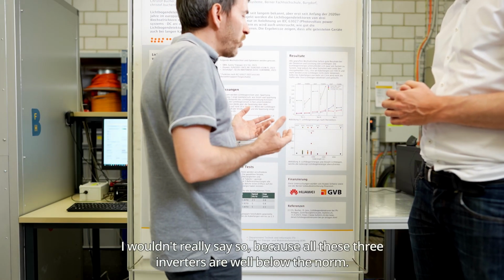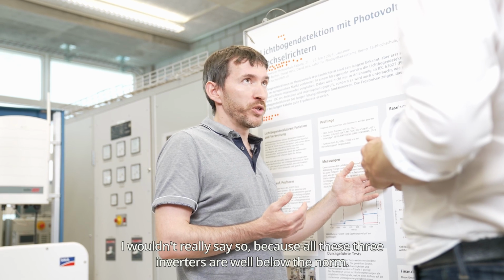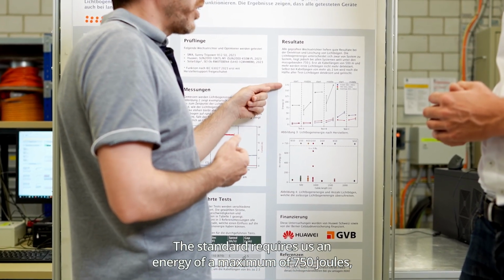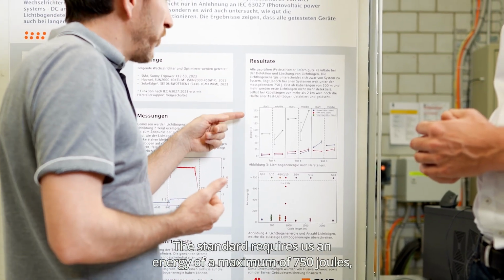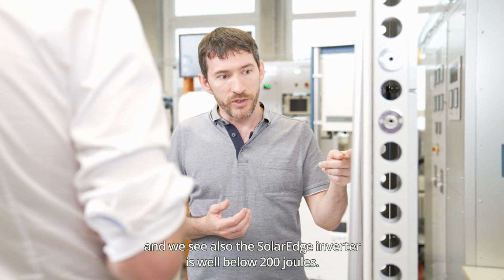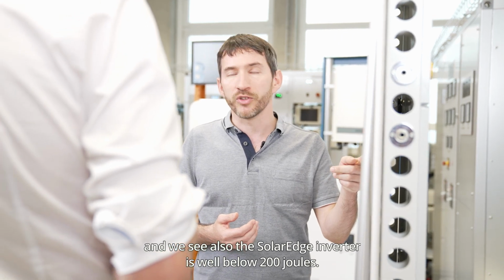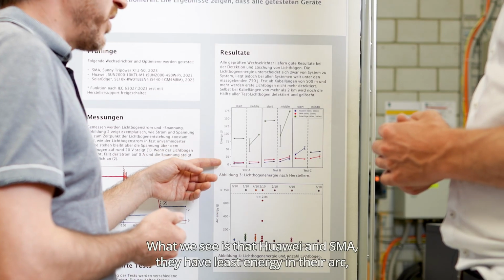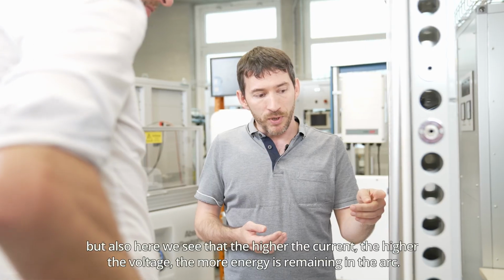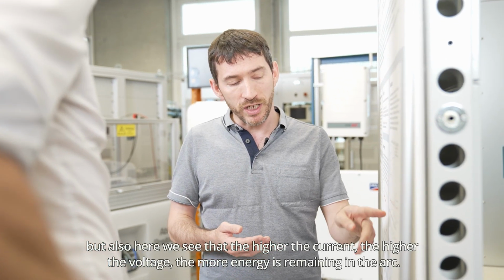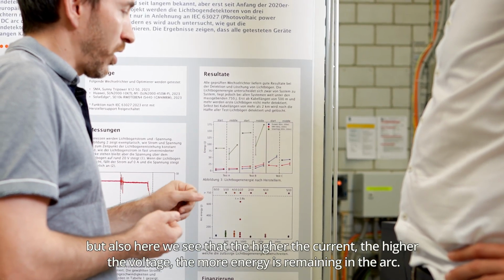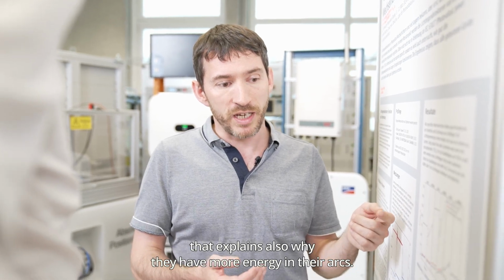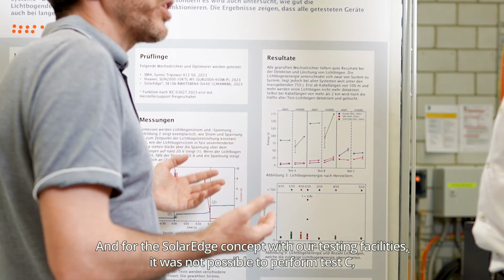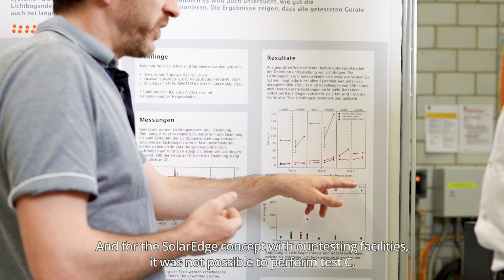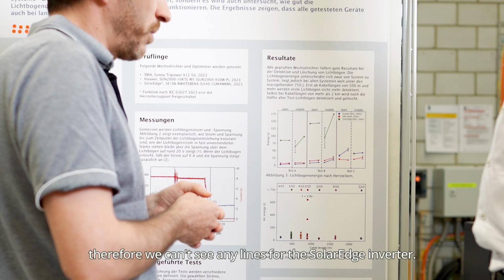I wouldn't really say so, because all these 3 inverters are well below the norm. The standard requires us an energy of a maximum of 750 joules, and we see also the SolarEdge inverter is well below 200 joules. What we see is that Huawei and SMA, they have least energy in their arc, but also here we see that the higher the current, the higher the voltage, the more energy is remaining in the arc. SolarEdge has quite a different concept. That explains also why they have more energy in their arcs. And for the SolarEdge concept with our testing facilities, it was not possible to perform test C, therefore we can't see any lines for the SolarEdge inverter.